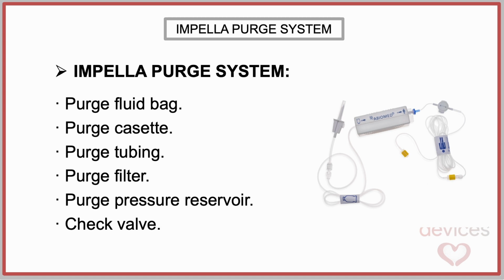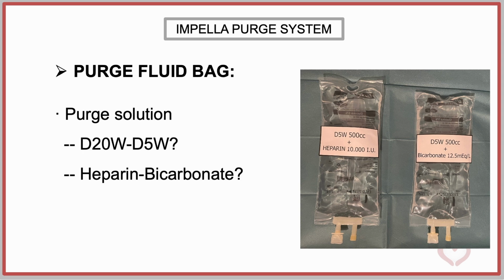Understanding each component of this circuit, starting at the purge bag and ending at the side arm on the Impella plug, is essential for safe bedside management and for troubleshooting alarms related to purge flow or pressure. At the beginning of the circuit lies the purge fluid bag, which contains the purge solution. In the initial instructions for use of the Impella CP device, the recommended purge solution consisted of 20% dextrose to achieve higher viscosity, combined with heparin at concentrations ranging from 25 to 50 international units per milliliter.